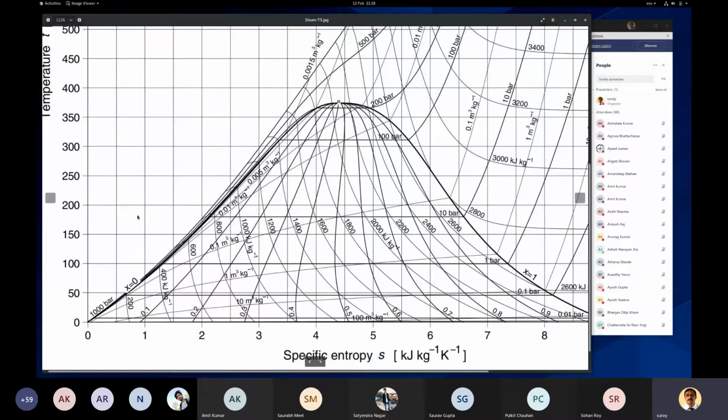So if the temperature of the liquid water is given, you look up the saturated liquid chart, get the property of enthalpy and use that enthalpy even if the liquid is not on the saturation line. That is an established way of working. But that luxury you don't have for steam. For steam, you have to know the pressure and temperature and find out the property.